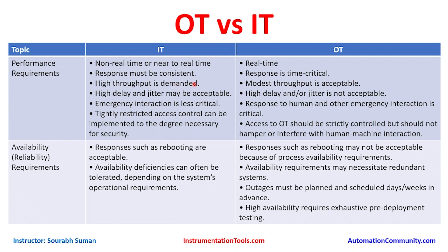High throughput is demanded in IT due to higher data volumes — we typically need 1 Gbps, 10 Gbps, or 100 Gbps links. But this is not required in OT. In OT, a 100 Mbps network is sufficient because OT systems barely consume four to five Mbps maximum throughput in a 24-hour period. The commands and data volume are pretty low unless backups are running.